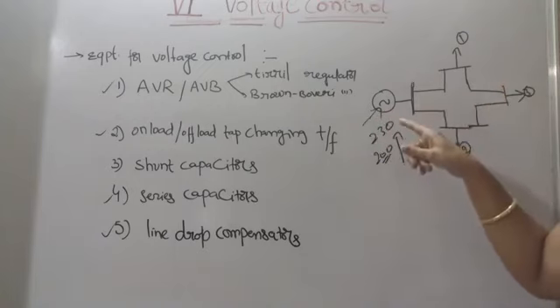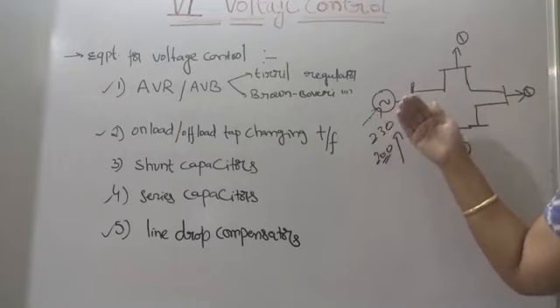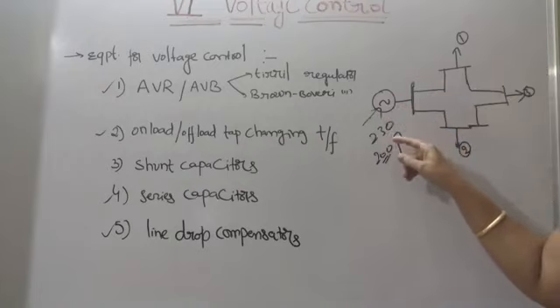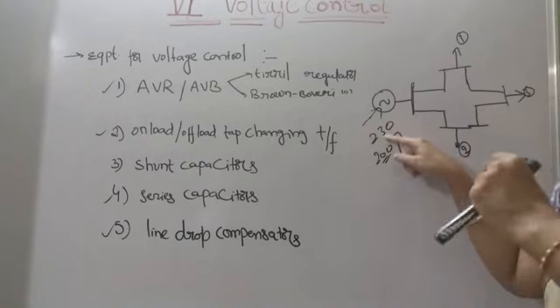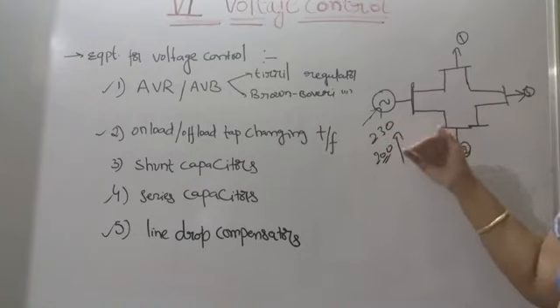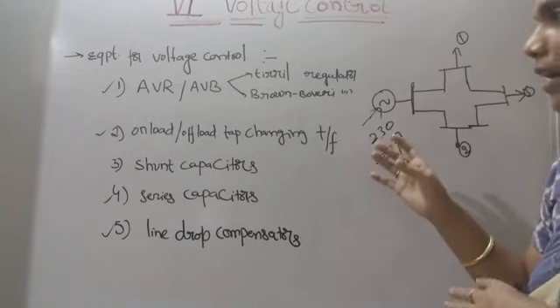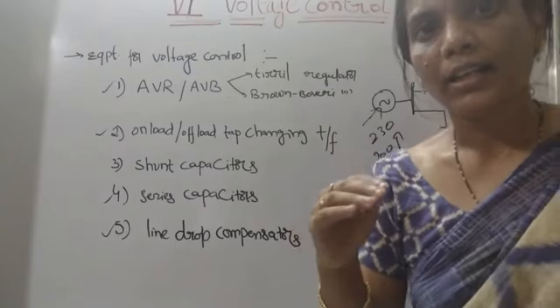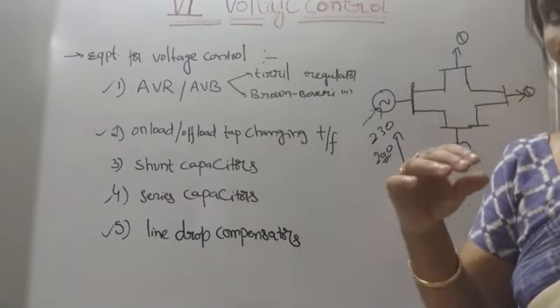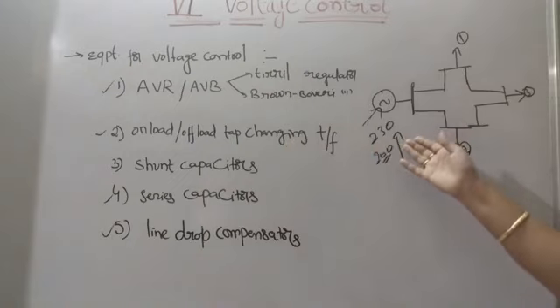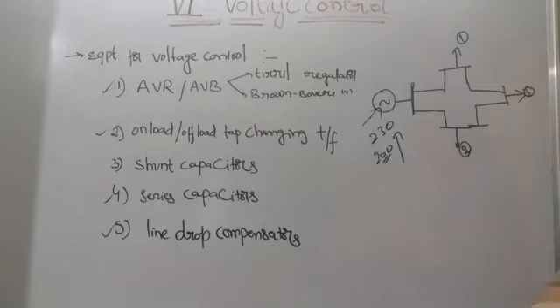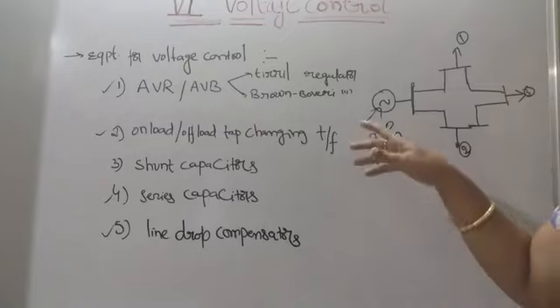When the voltage at the generator is less than the permissible limit, for example 218 volts instead of 230 volts, it will automatically increase the field winding excitation up to getting this value to 230 volts. That is the purpose of the AVR.